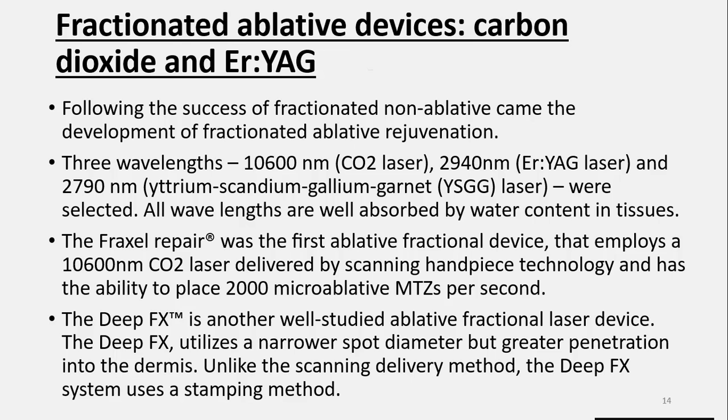The Fraxel Repair was the first ablative fractional device that employs a 10,600 nanometer CO2 laser delivered by scanning handpiece technology and has an ability to place 2,000 microablative treatment zones per second.